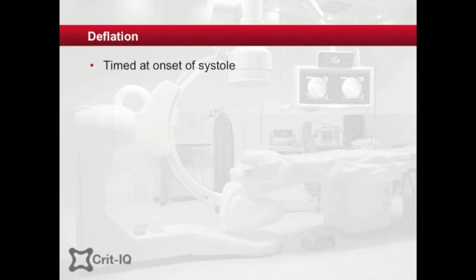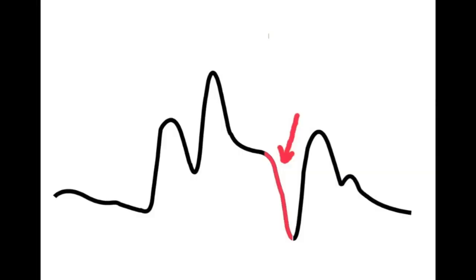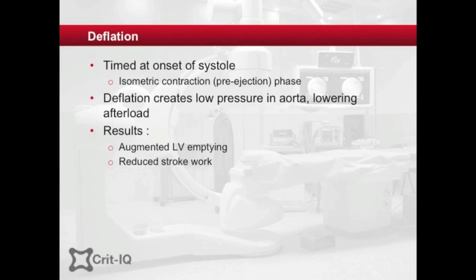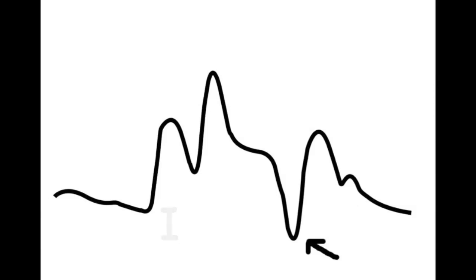Deflation of the balloon should occur at the onset of systole during the pre-ejection phase of isovolumetric contraction, when the left ventricle is building enough pressure to overcome the pressure in the aorta. Rapid deflation of the balloon creates an area of lowered pressure in the aorta just ahead of left ventricular ejection. This augments left ventricular emptying, reducing the left ventricular stroke work. With correct timing, the assisted end diastolic pressure should be a sharp V and lower than the patient's own end diastolic pressure.